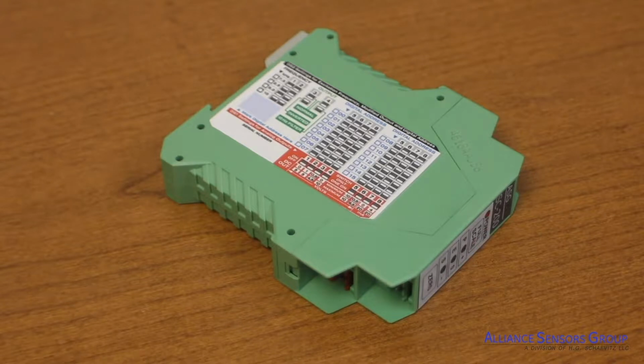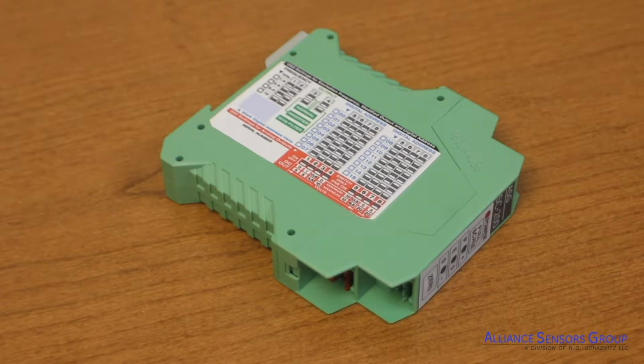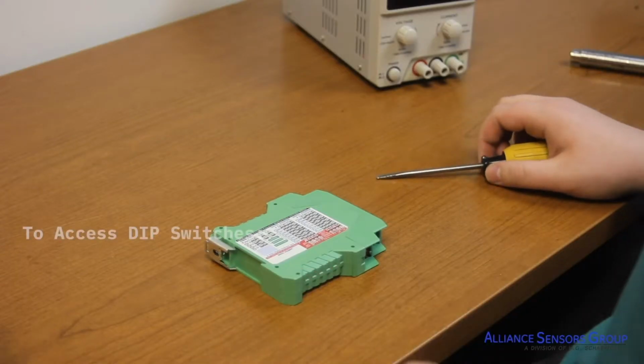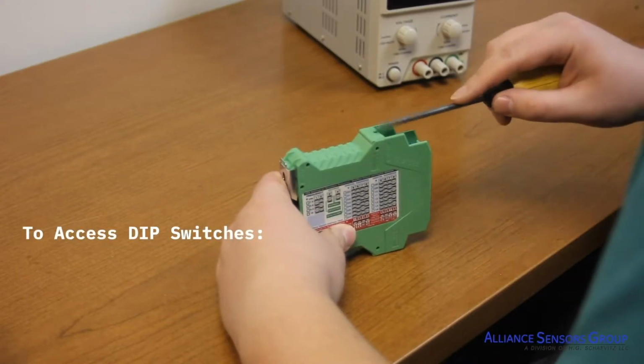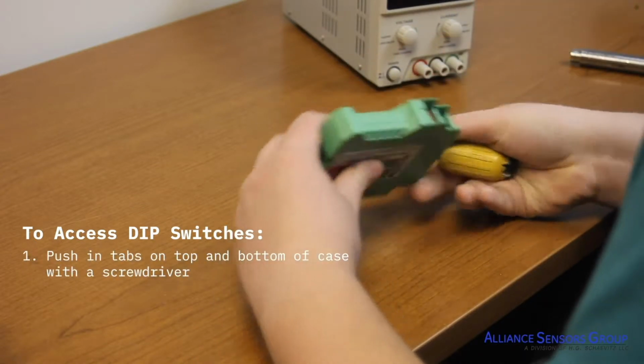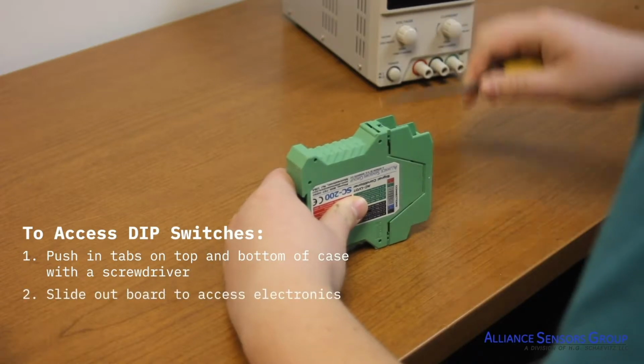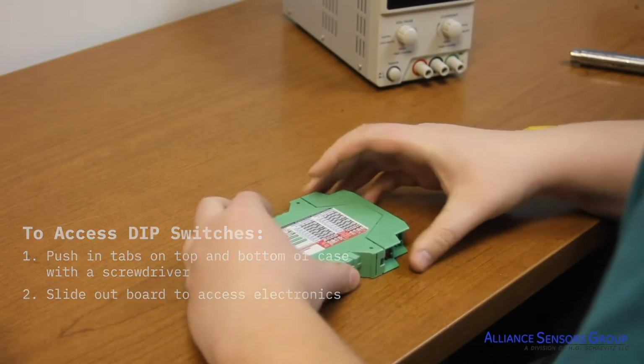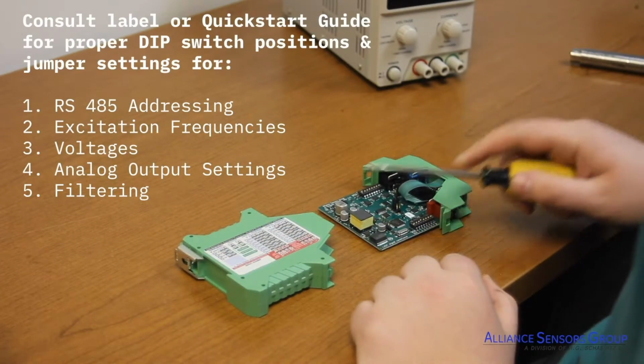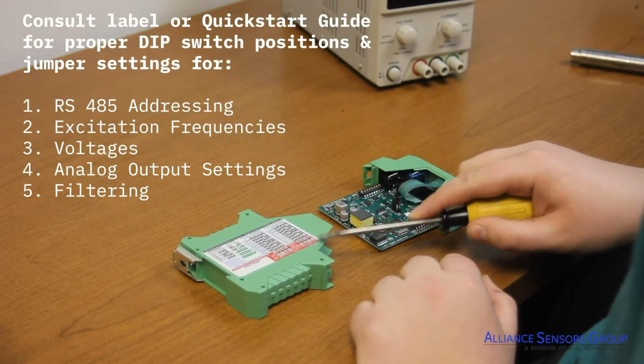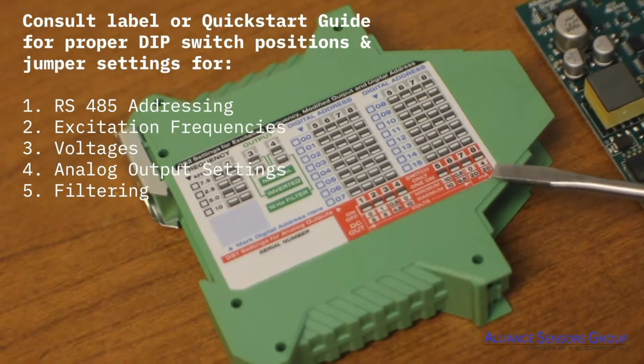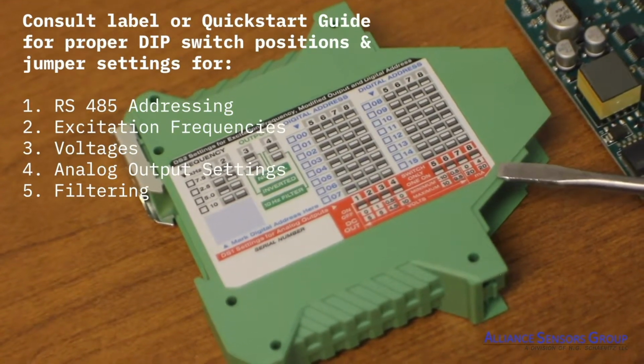Before proceeding, factory default settings are adequate for most standard industrial LVDTs, and no adjustments are typically required. In the event that the LVDT requires different settings from the factory defaults, you will need to adjust the SC-200 to match your particular LVDT requirements. To perform these adjustments, the dip switches can be accessed by pushing in the tabs on both the top and the bottom sides of the case with a small screwdriver, then sliding out the board to access the electronics. Please consult the label on the case or the Quick Start Guide instructions for proper dip switch position and jumper settings for RS-485 addressing, excitation frequencies, voltages, analog output settings, and filtering.